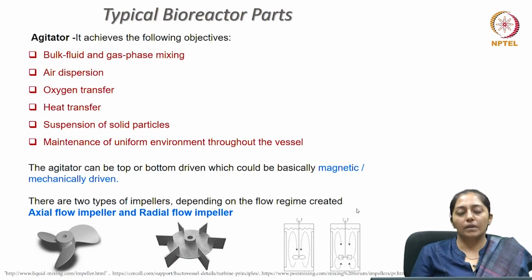Now, talking about the agitator, it achieves the objectives of bulk liquid and gas mixing, provides dispersion of air, and provides oxygen transfer from the gas bubble to the liquid broth. It facilitates heat transfer throughout the liquid broth and also from the liquid broth to the external coolant, which is circulating to maintain the temperature of the reactor.